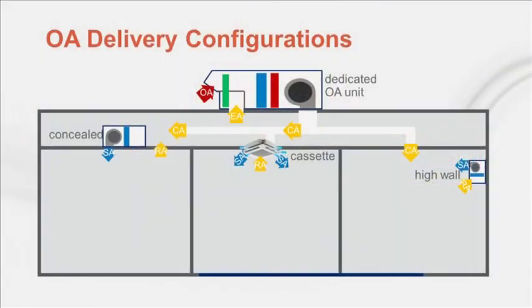Standard 62.1 defines how much outdoor air is required in each zone. The challenge for the design engineer is how to distribute that amount of outdoor air to the individual zones. This slide shows three common ways in which outdoor air is delivered in a VRF system. The left-hand zone shows outdoor air delivered to the ceiling plenum near the intake of a concealed indoor VRF terminal. The outdoor air mixes with the recirculated air in the plenum before being drawn into the terminal.